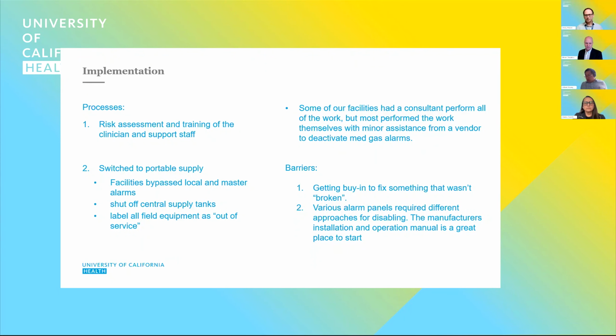Disable your field alarms and then shut your valves. We actually had an issue with St. Vincent, the first major hospital we shut off, where we didn't do our research quite well enough and thought we had some of the alarm channels disabled when they weren't. As the system bled down after being shut off, some of the alarms started going off for no apparent reason. So definitely figure it out for each type of alarm, especially in older facilities where you might have had a lot of growth over time — we had 5 different styles of alarm we had to figure out.